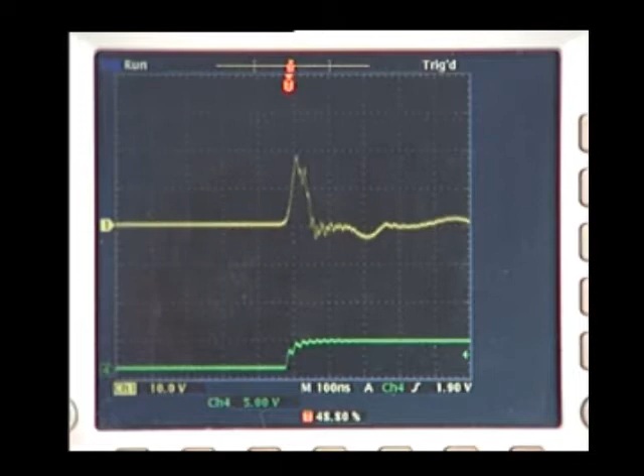Here is a unit simulating a product that failed when it was subjected to the standard CE ESD immunity test. Normally the LEDs flash in sequence, but during the immunity test the LEDs behaved erratically. We will now check this unit with the EMPulse power set to high and with frequency set to random.